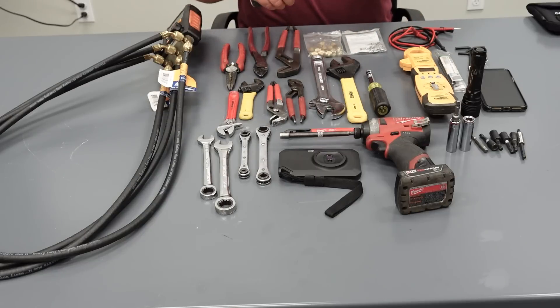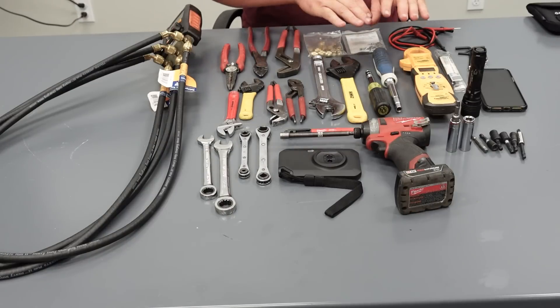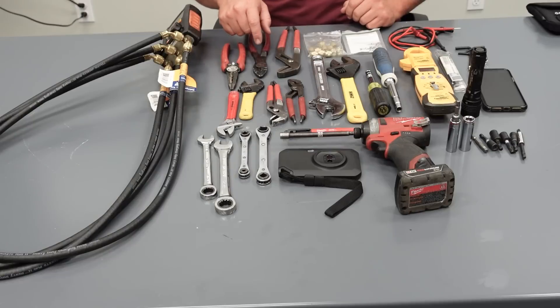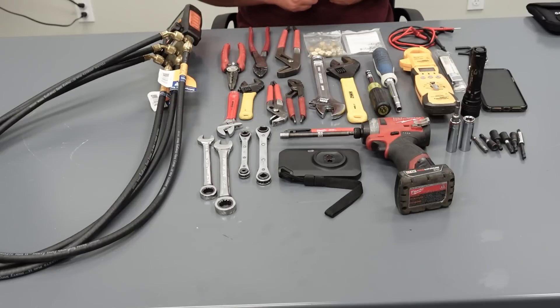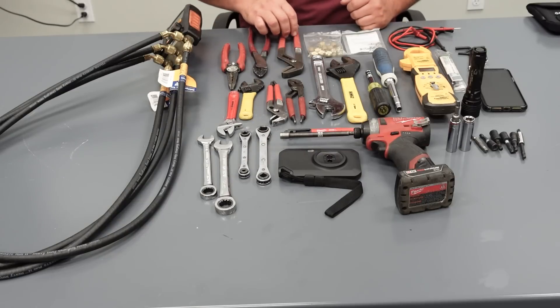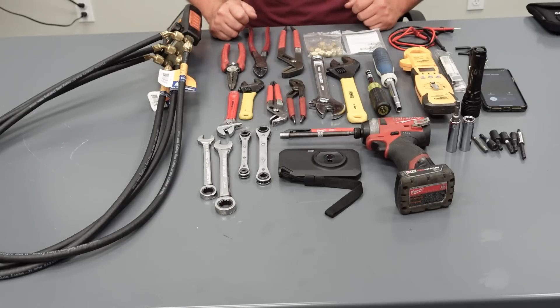I have a multi-combo deal where it has multiple tools in a small package, so that way you're not taking in a whole nut driver set into the store. I have a pair of wire strippers, a pair of wire crimps — especially make sure that you have an insulated crimper, not just a non-insulated one. Most of the things we work on here in supermarket refrigeration have insulation around the crimps, and if you use the non-insulated one it'll actually pierce those. I also carry a couple of channel locks because sometimes you need to get into really small spaces.